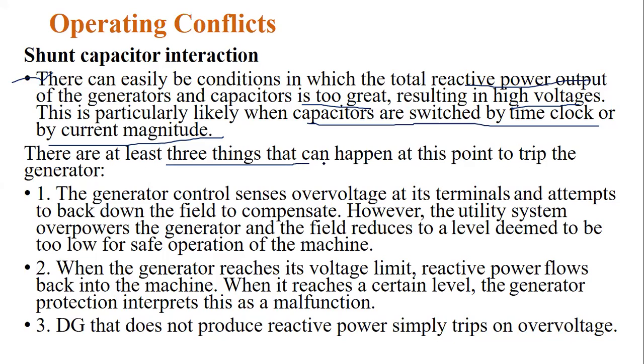So in this case, you know what the main equipment in the power system is: the generator. So we need to protect the generator from this case. The capacitor and the generators can take three precautions like this. The first: the generator control senses the over voltages at the terminals. The generator also knows whether the load is increasing or decreasing. Based on that, there are some excitation techniques as well as some speed control techniques in the system, and based on those the generator is operated. So the generator is aware of the load side voltages also. That is the first case.